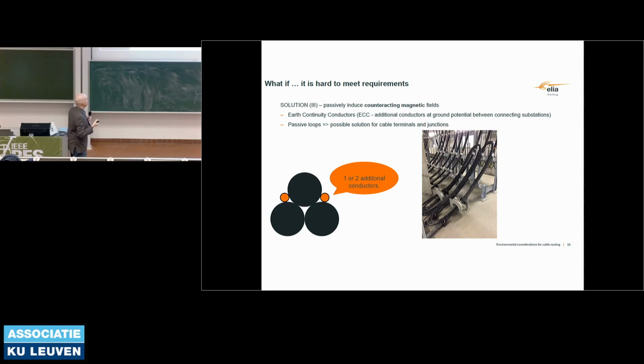Some easier things we could do: if you would ask any colleague to talk about the earth continuity conductor, nobody would understand it. It's called le câble de drainage, but the official English term is earth continuity conductor. So even with a cable route, you have your three phases, and you would draw one or two more underground conductors at ground potential from substation A to substation B. Any surplus magnetic field would induce a voltage difference, which would induce a circulating current to even more dampen the radiated magnetic field. This is something that's done at almost any cable route, especially in urban environments.